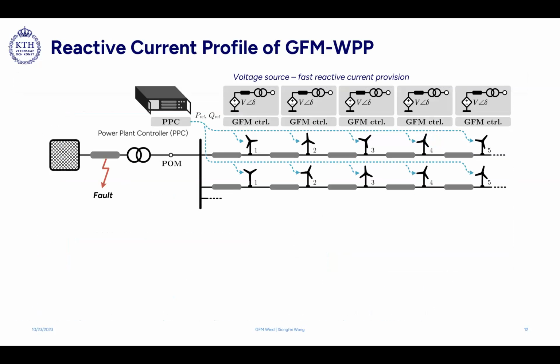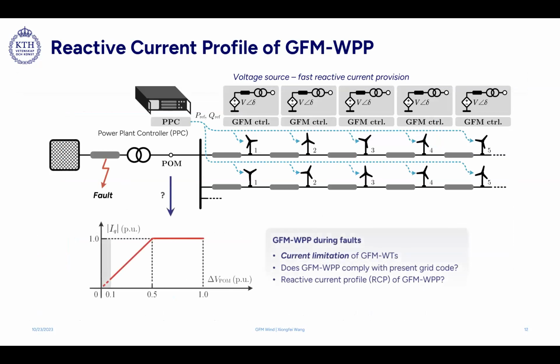Yeah, in the last part, I want to talk a little bit about the reactive current. This is also related to the voltage support from the grid forming wind power plant. The question is very simple. When we have a grid forming wind power plant, we also have current limitation in the power semiconductor devices. With this current limitation, can we still meet the present grid code on reactive current injection? And what will the reactive current profile of the grid forming wind power plant look like? In this case, we didn't consider any additional STATCOM in the wind power plant, but only considered grid-forming wind turbines together with the power plant controller.